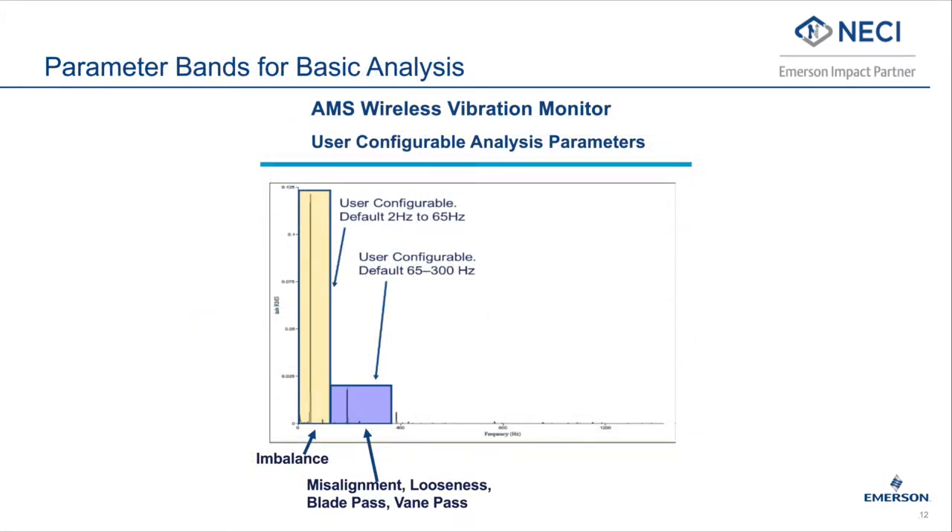In addition to PeakVue Plus, the AMS Wireless Vibration Monitor provides parameter bands that help to determine basic vibration diagnostics at lower frequencies. These bands are based on turning speed, so features are available for fixed speed applications to diagnose imbalance, misalignment, looseness, blade pass, or vane pass issues. Full vibration analysis capabilities are available when AMS Machine Works software is included with the wireless system.